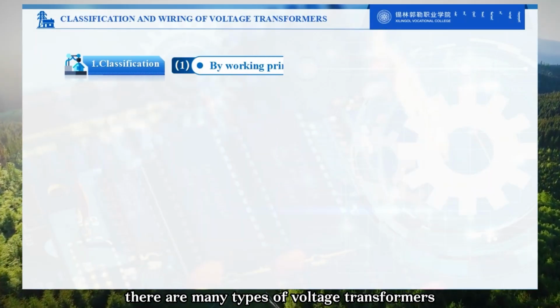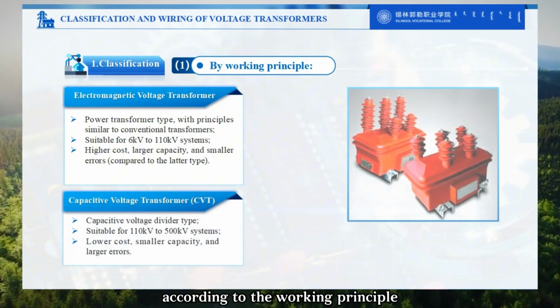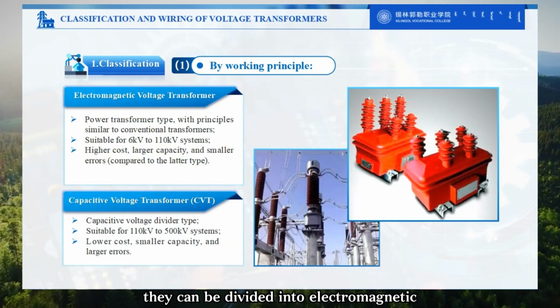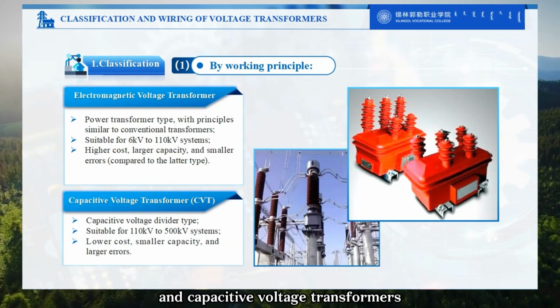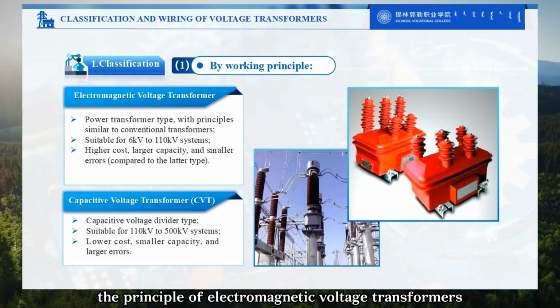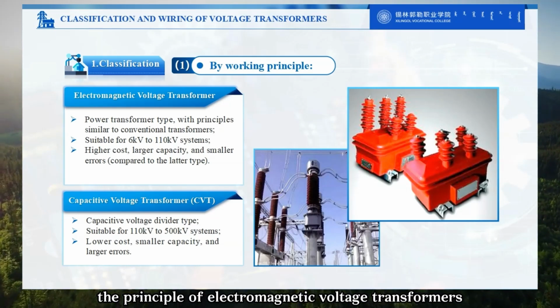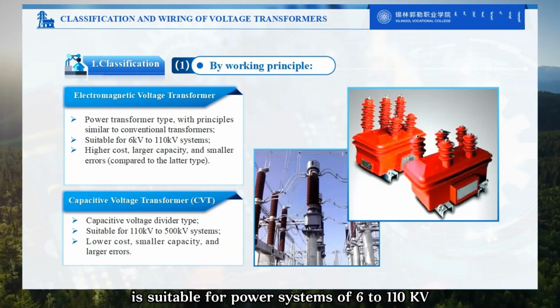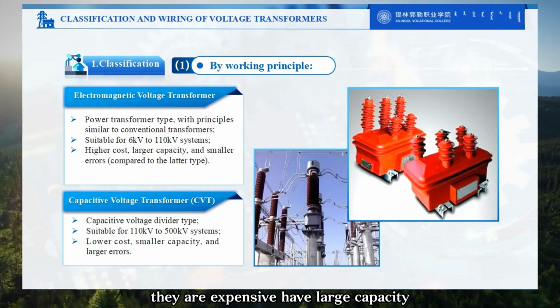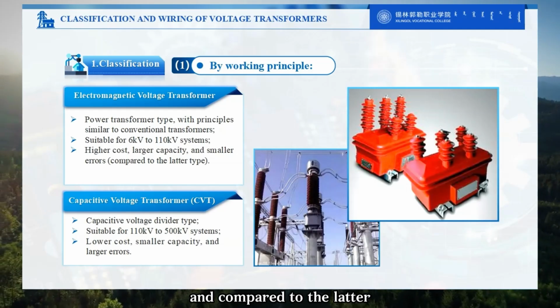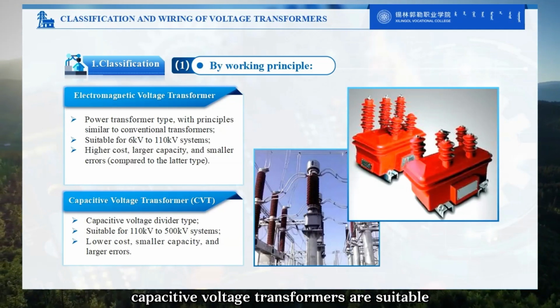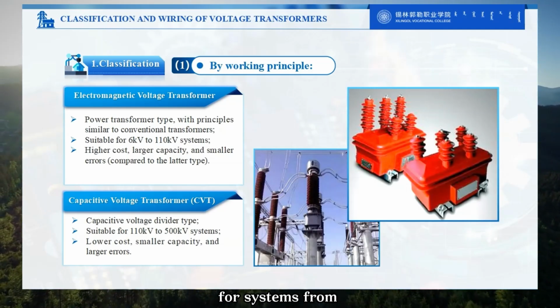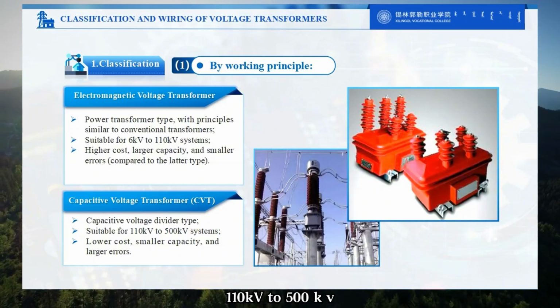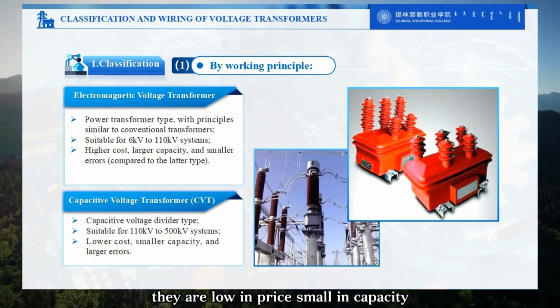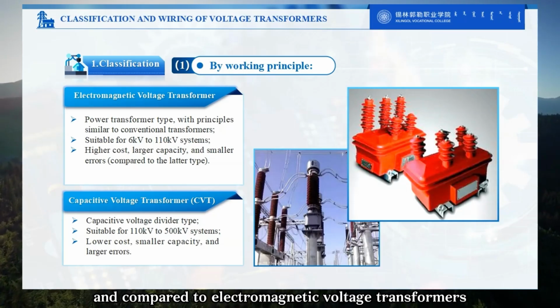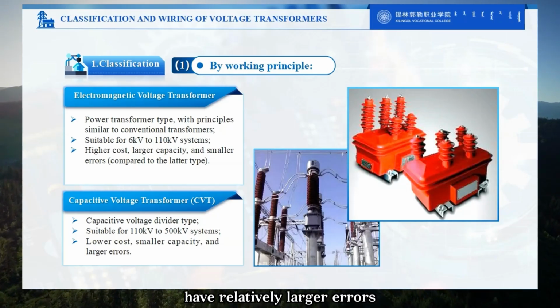There are many types of voltage transformers. According to the working principle, they can be divided into electromagnetic voltage transformers and capacitive voltage transformers. Among them, electromagnetic voltage transformers are suitable for power systems of 6 to 110 kV. They are expensive, have large capacity, and compared to the latter, have smaller errors. Capacitive voltage transformers are suitable for systems from 110 kV to 500 kV. They are low in price, small in capacity, and compared to electromagnetic voltage transformers, have relatively larger errors.